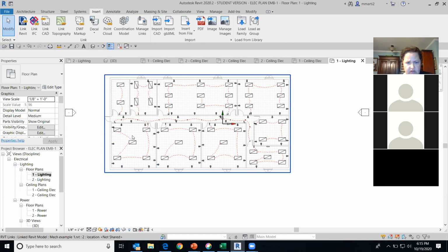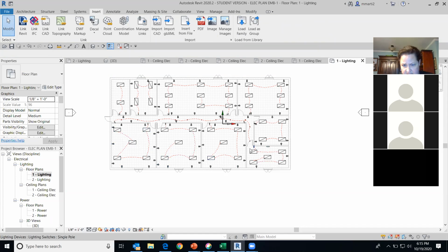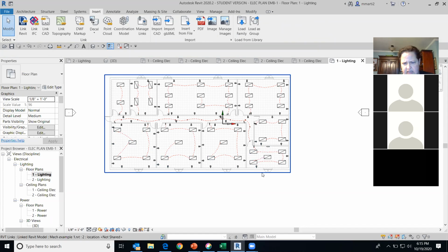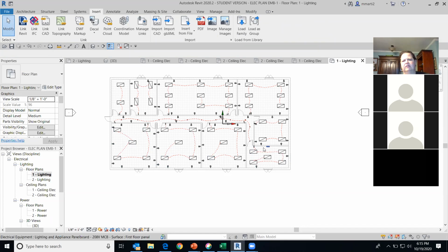Same here, there's 5 here. Round that up to 6 and kind of distribute that. This tiny little room has way too many lights. The calculation should not have come out for 5 lights in this room. This room is very similar to this room over here.